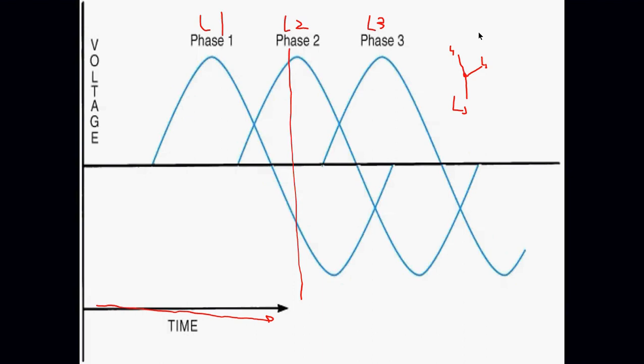Are those like the motors that are in cooling towers? Well, it depends, you can have a motor on a three-phase circuit where you're only using L1 and L2, so be careful about that.